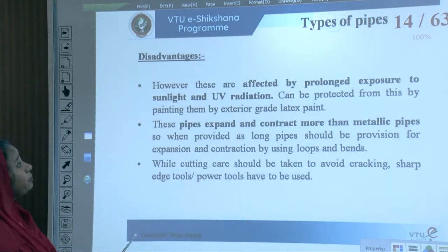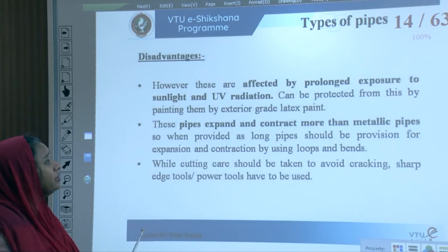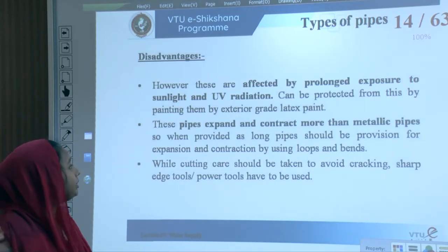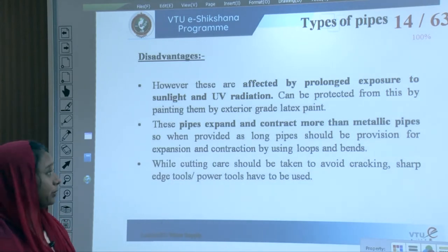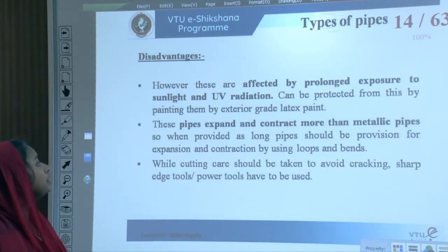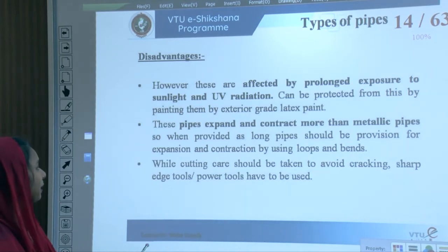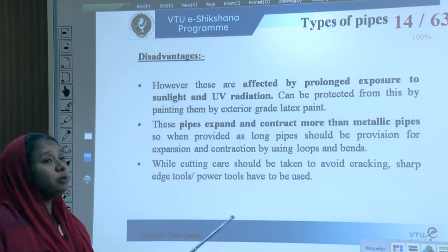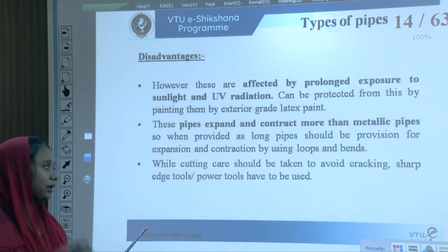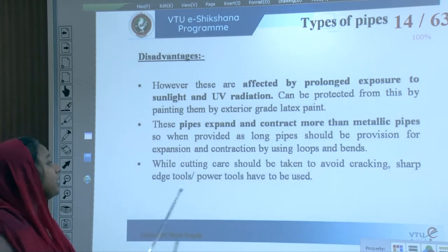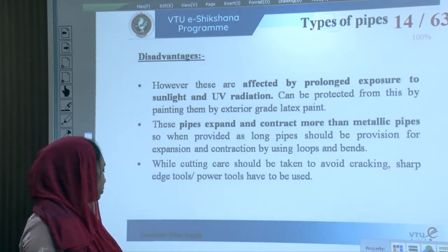A disadvantage of CPVC pipes is that they are affected by prolonged exposure to sunlight and UV radiation, so they must be protected using exterior-grade latex paint. These pipes also expand and contract more than metallic pipes, so when provided as longer pipes, provision for expansion and contraction must be made using loops and bends. Care should also be taken to avoid cracking, using sharp-edged tools for cutting.